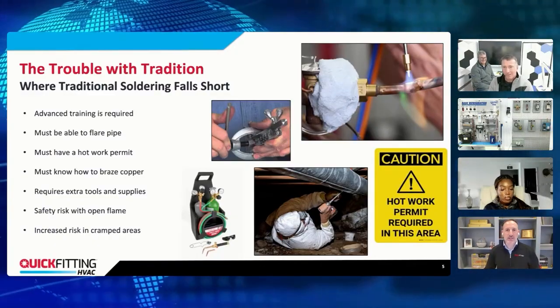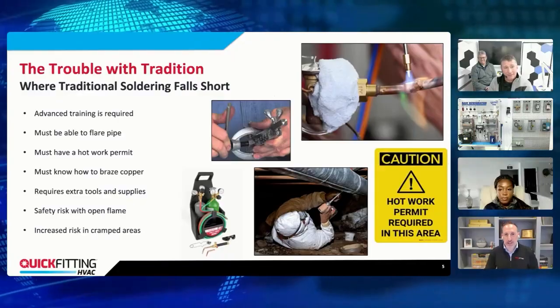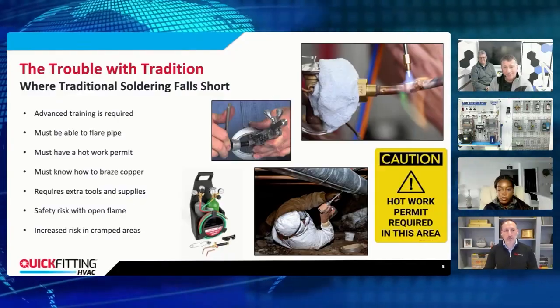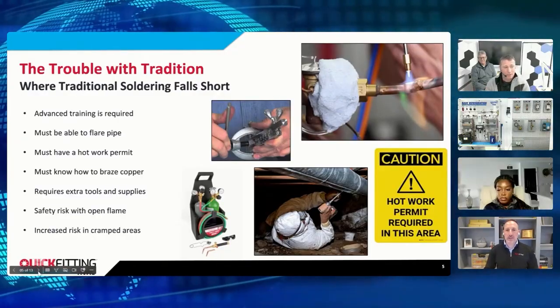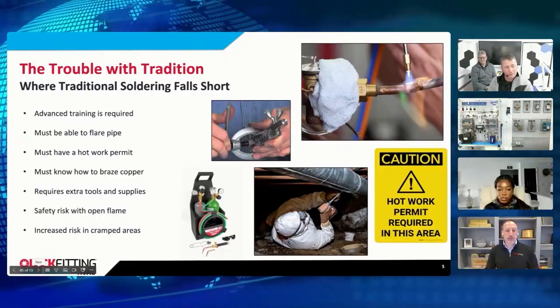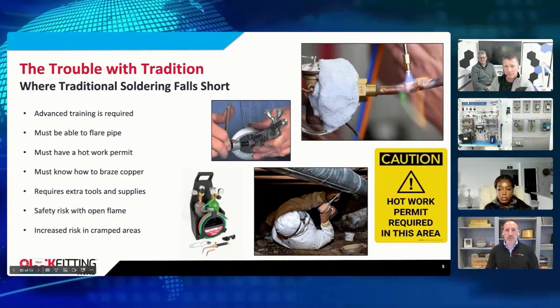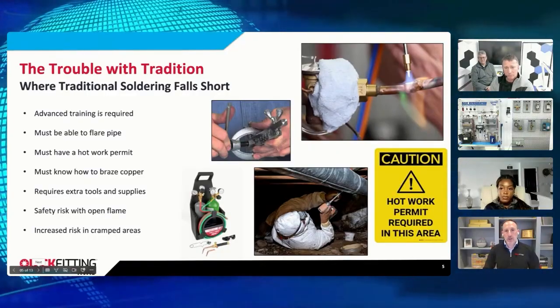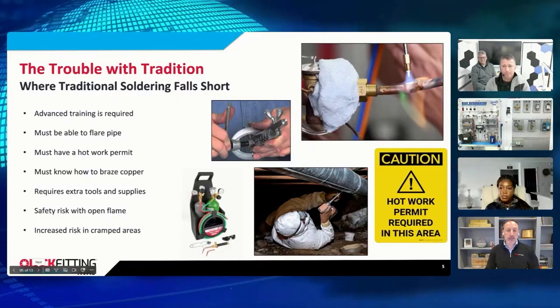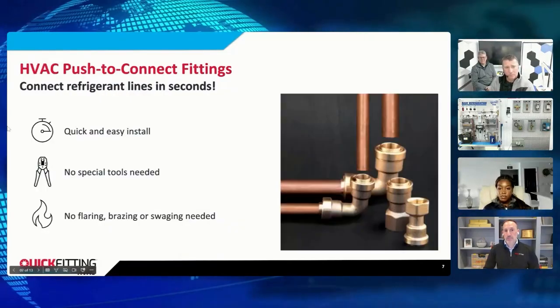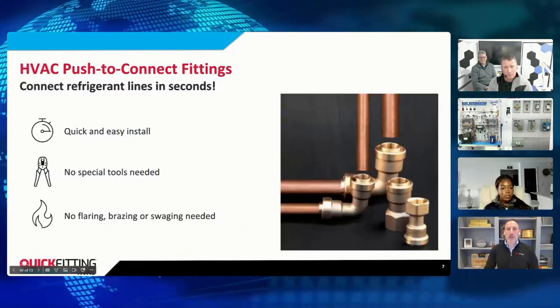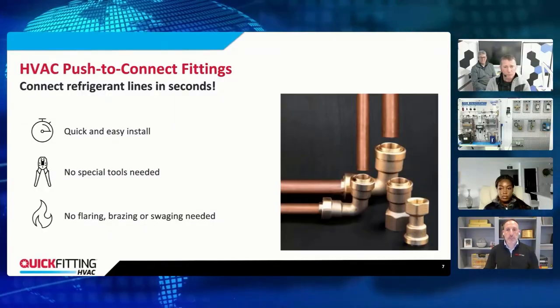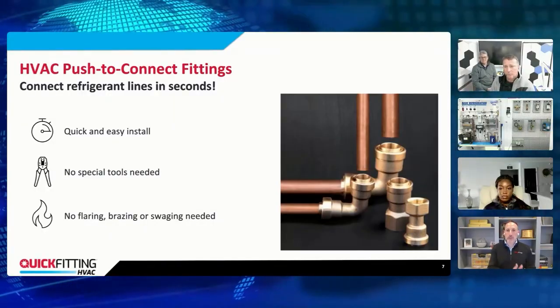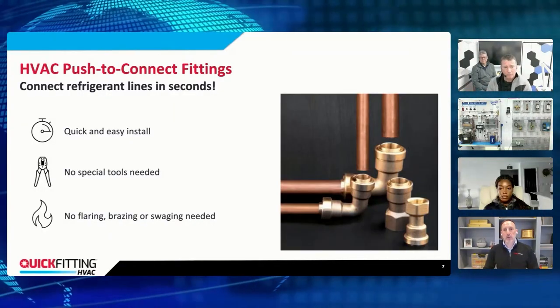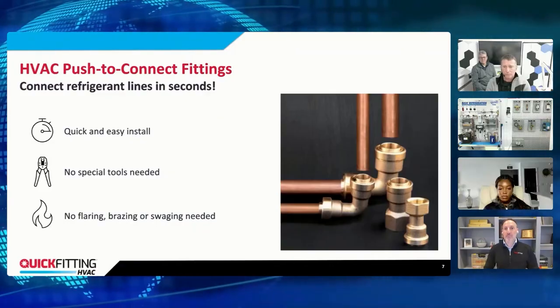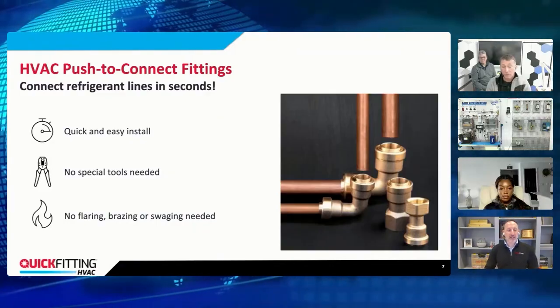We've got a UL product that's a push-to-connect fitting. It doesn't take the tools, it takes away some of the safety risks, and gives you a consistent and reliable result every time you use a push-to-connect fitting for HVAC. Is it something you always use? Probably not. But in certain situations, it's great when done correctly, and we'll go through what that means.